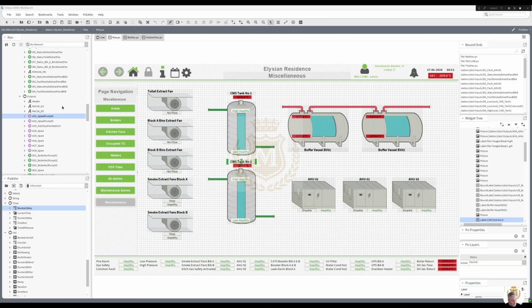These are all the outputs that we set up. We have no outputs for any of these fans at all, we're only monitoring them. So they're fed from somewhere else, don't know if it's MCP2 or where from yet. At the moment, this controller and the points we've got are monitoring only. Maybe when we bring in MCP2 and link them together, we may get more points to populate this information with.